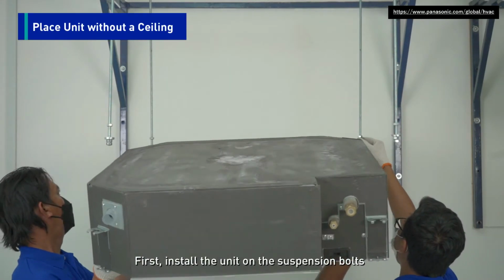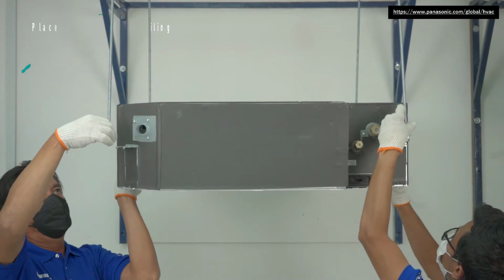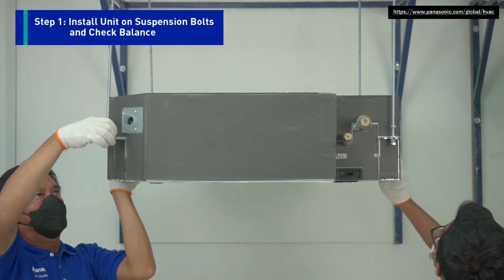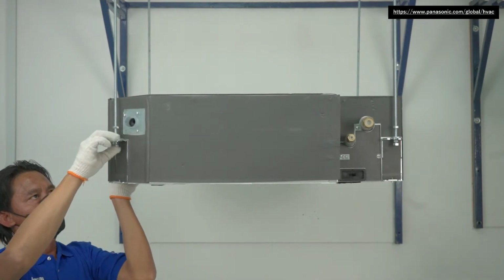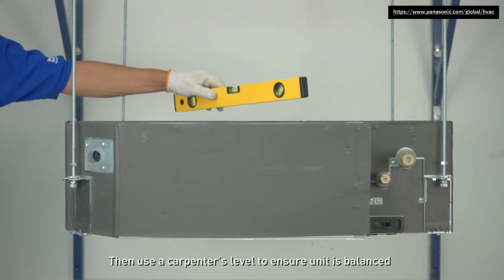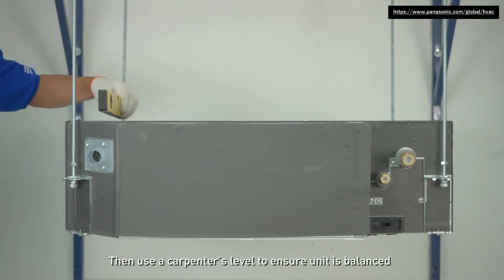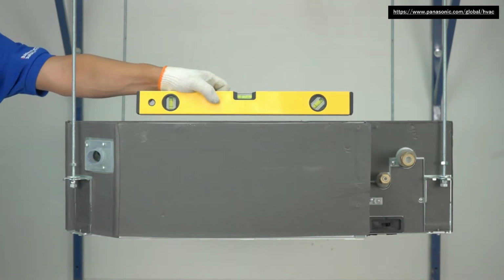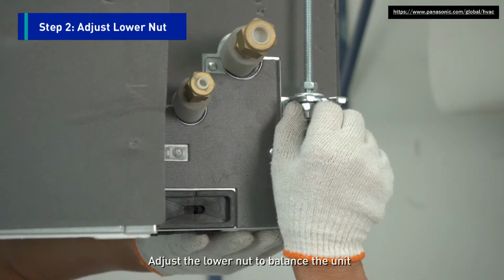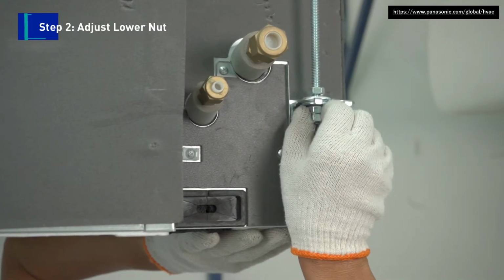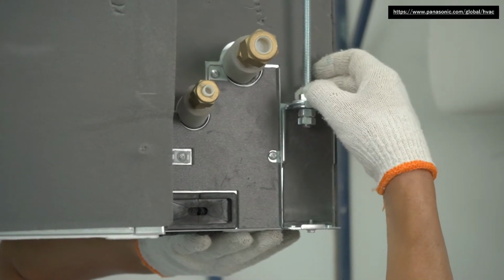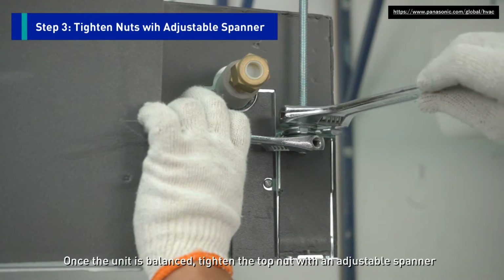First, install the units on the suspension bolts. Then, use a carpenter's level to ensure unit is balanced. Adjust the lower nut to balance the unit. Once the unit is balanced, tighten the top nut with an adjustable spanner.